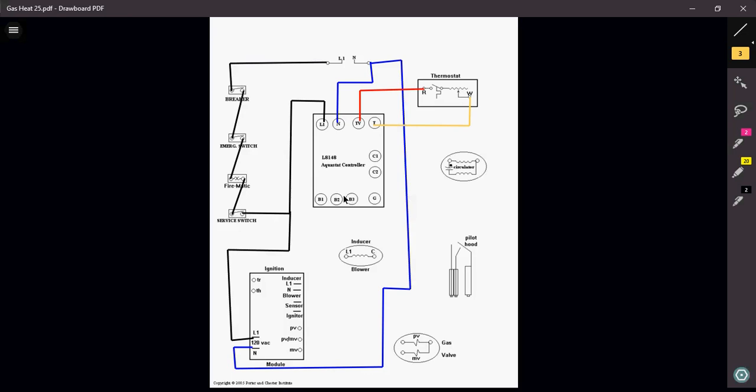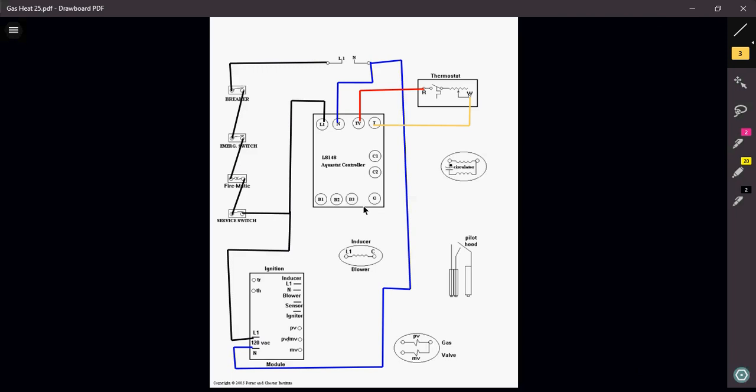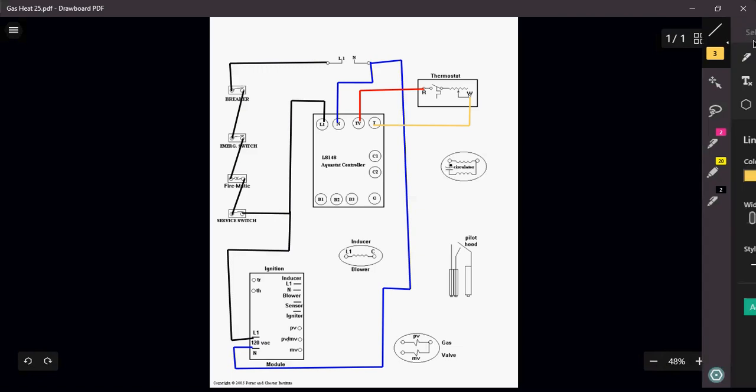Remember now with an 8148 Aquastat, this is a triple Aquastat here. I got B1, B2, and B3. On these aquastats, B1 and B2 is for millivolts for millivolt gas valves. B1 and B3 would actually give me my 24 volts to power up my 24 volt gas valve. Those are my two terminals that I want to use in this application.